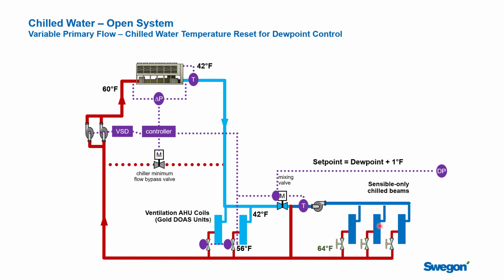So if the dew point goes from 57 to 58, then we take 58 degrees plus 1 and reset our supply temperature just to the chill beams, not to the air handling units, just to the beams, and keep this water temperature above the dew point. That's going to do a couple of things for you. First, you won't have any condensation because the chilled water is staying above the dew point. And secondly, you'll get some level of cooling.